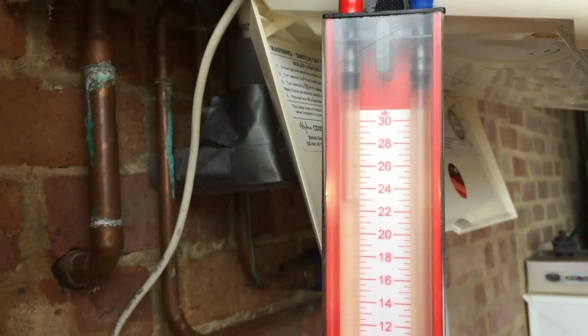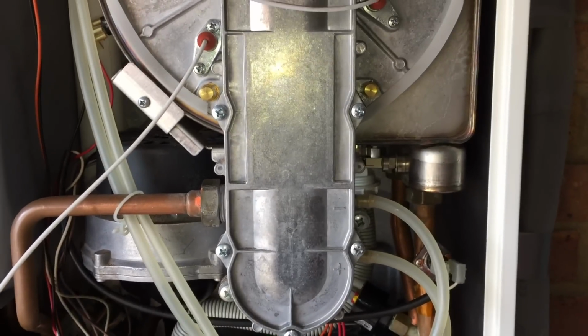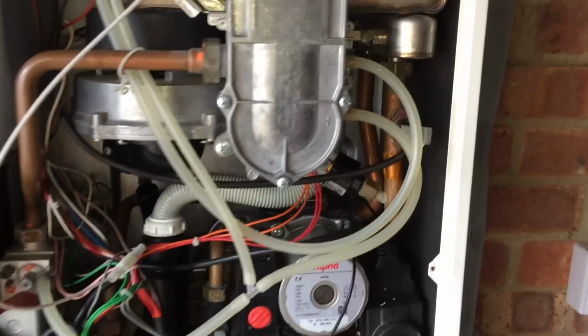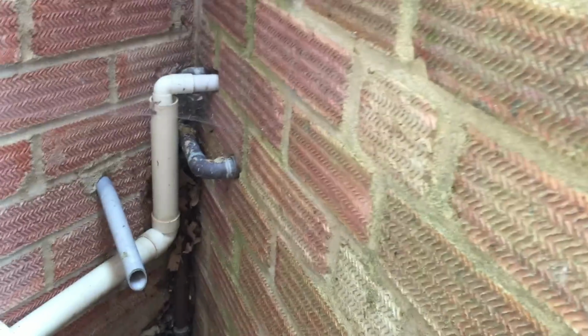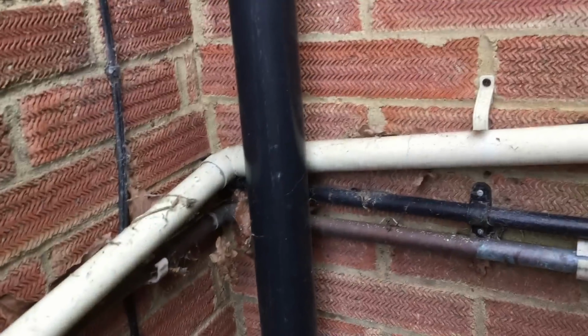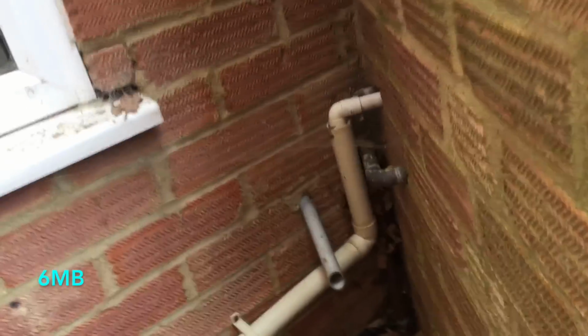Oh, it's locked out. There we go. So, let's find out why the gas pressure's wrong. Okay, so the lady's now emptying the cupboard for us to check the gas. I've already done the quick visual. I mean, it's 22 coming through the wall there, straight up to the boiler. It's 22 there. I mean, don't get me wrong, there's a few elbows on it, but not enough that would cause it to drop to 16 millibar because we've only got, what have we got here? Maybe 3 meters of pipe plus 1, 2, 3, 4, 5 elbows. So it's not exactly a huge amount.